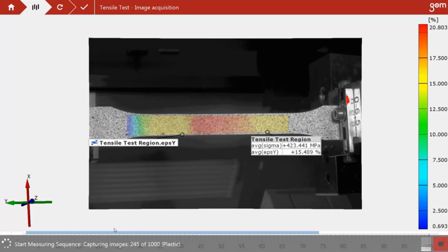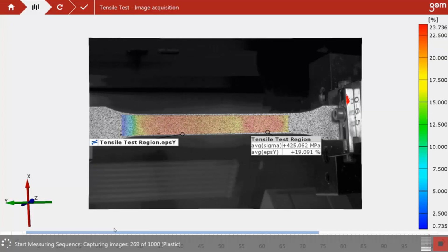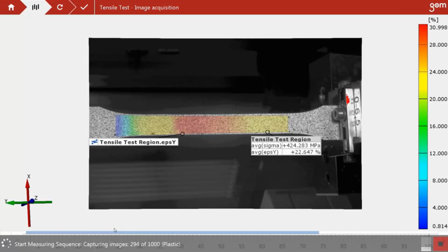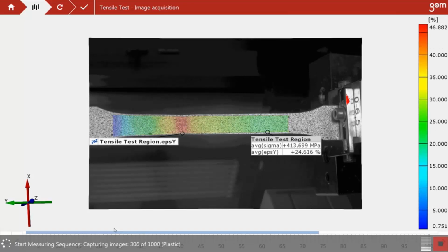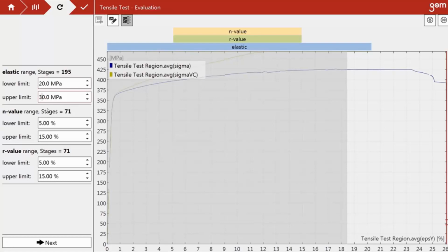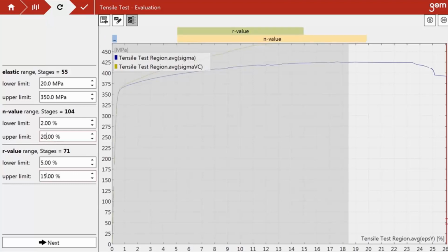Because we already have basically the question marks for the data points that we're trying to solve for. The system is going to script a lot of the data capture. So once it goes to the full test, then it will start adding them into the project that we created in Zeiss Inspect Correlate.